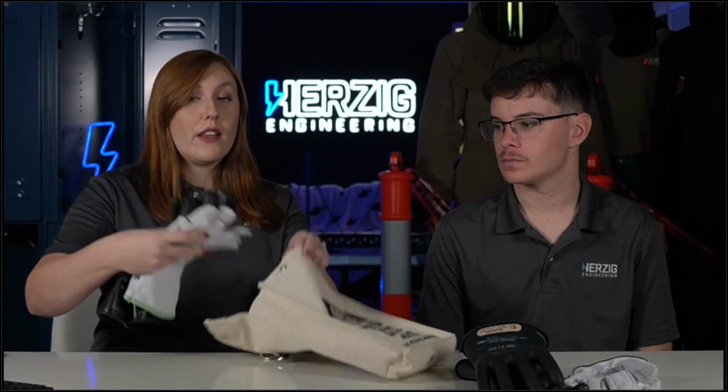That's something that we can definitely talk about more if you have more questions. But last thing about these gloves before we slip back into the slide deck, and looking at the time, we're going to be moving right along here. Whenever you store them, to get your work done, you take them off, store them right side out. You can put your leather gloves as well back into the container or the case, not folded up, not rolled up, nice and flat, and kept in a safe environment like a locker or a desk or a work cart. Don't throw it in with your normal tools that could puncture or damage those gloves. Yeah. Okay. All right, let's dive back into this presentation.